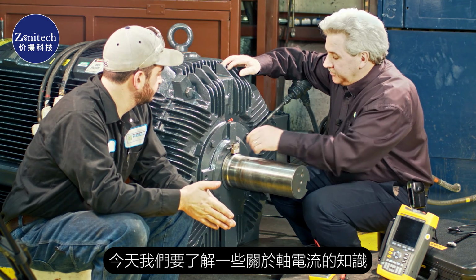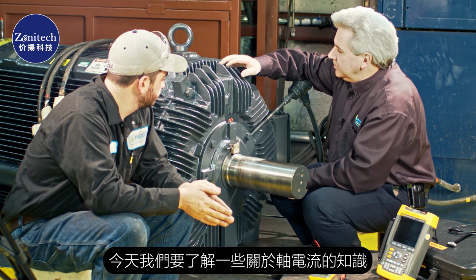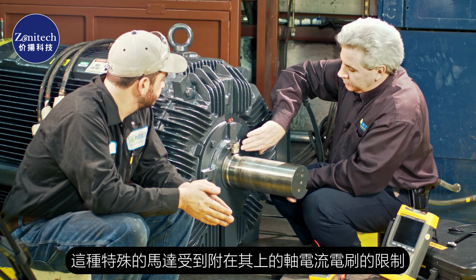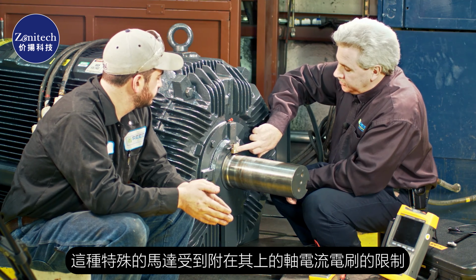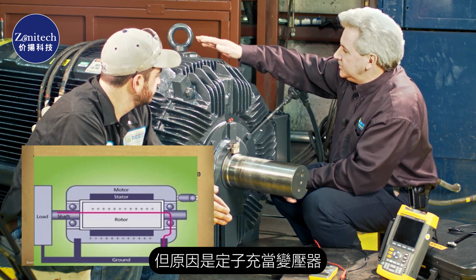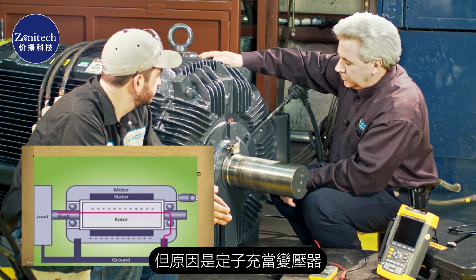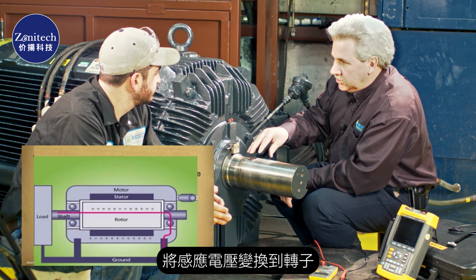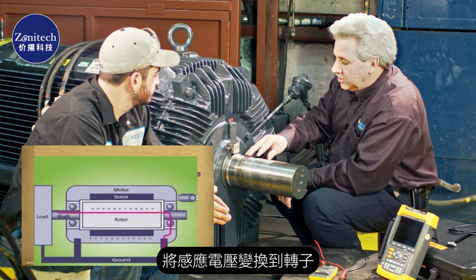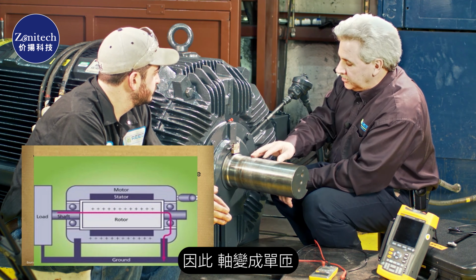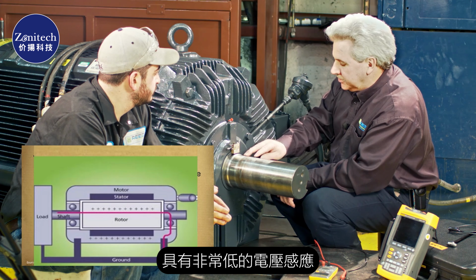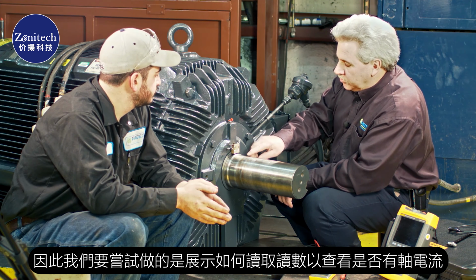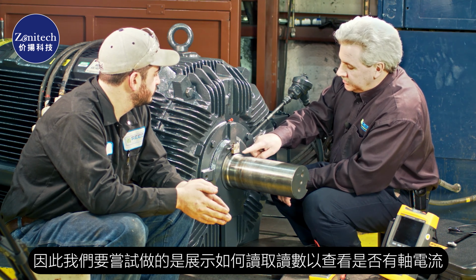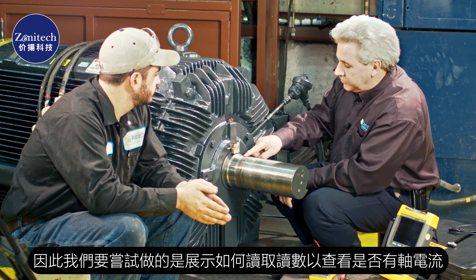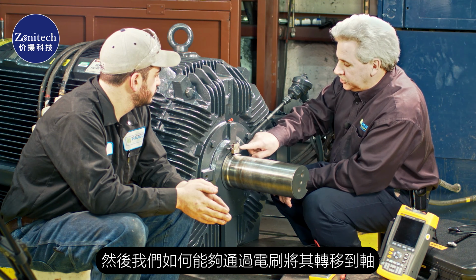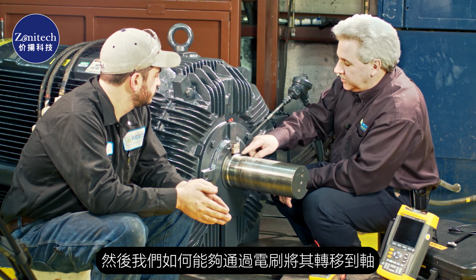Brett, we're going to find out a little bit about shaft currents today. This particular motor is mounted with a shaft current brush attached to it, but the reason for it is that the stator acts as a transformer, and it transforms an induction voltage into the rotor. So the shaft becomes a single turn that has a very low voltage induction, but it has a high current.